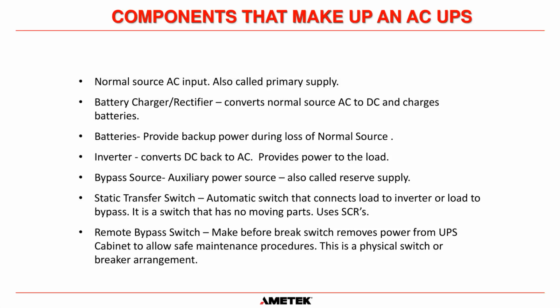And then the last term that we're going to discuss is the remote bypass switch, or a bypass switch, which is a make before break mechanical switch that removes power from the UPS cabinet to allow safe maintenance procedures. It's always a physical switch, or it could even be a breaker arrangement. You can have maybe a 3-breaker arrangement, or sometimes I've seen a 5-breaker arrangement where you have to open and close the breakers in a certain way to bypass the UPS cubicle itself and to make it power free for maintenance.